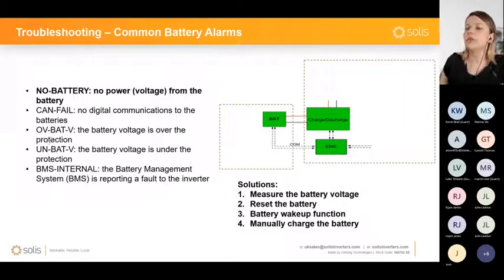You might have over voltage, OV-BAT-V, that's over voltage on the battery side when the battery protects itself, and sometimes it even disconnects itself when the inverter is pushing power into the battery, but the battery management system didn't yet limit the current that is being allowed to be put into the battery. This can happen, an over voltage battery alarm. This can be quite easily fixed, probably with firmware from the battery manufacturer, or even if from our side we lower the SOC to which the inverter will charge the battery.